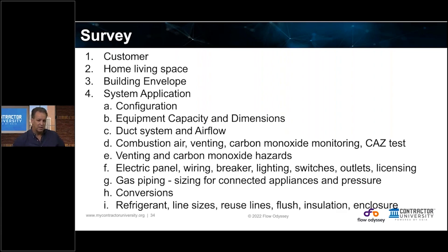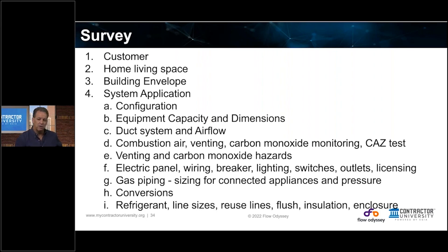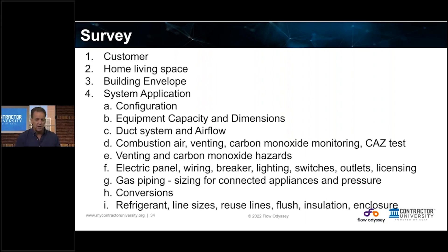Where we left off is talking about oil-to-gas conversions in certain areas of the country. You also have to look at the refrigerant lines — are you going to reuse them? What are the sizes, what type of refrigerant is out there, and what type will the new system use? If you're going to reuse the lines, do you need to flush them? Is that something code allows? Is there insulation missing off the lines? If the lines are snaked outside the house, are you going to put a line set enclosure on them and explain that to the homeowner?